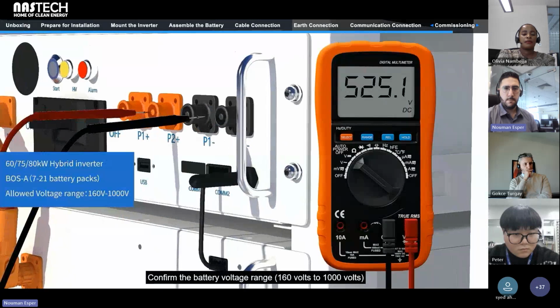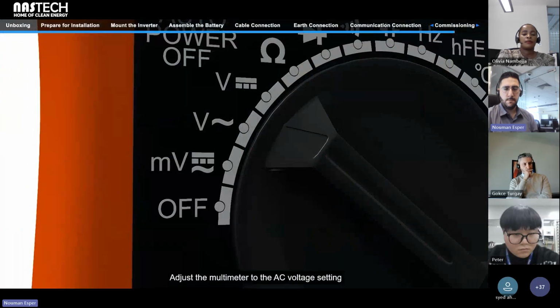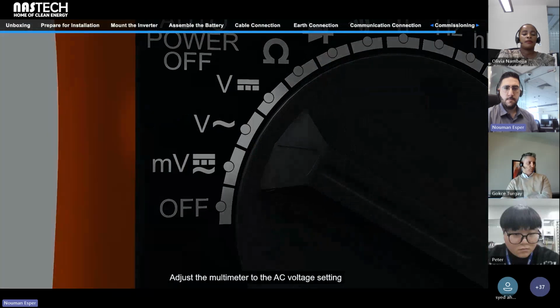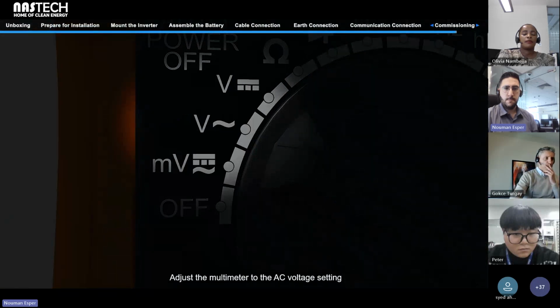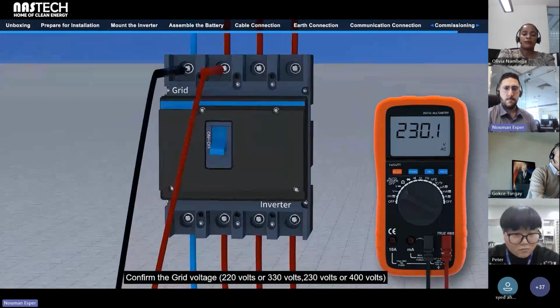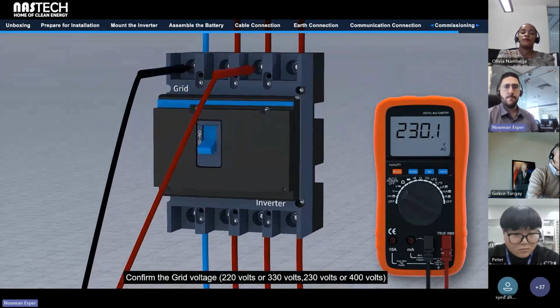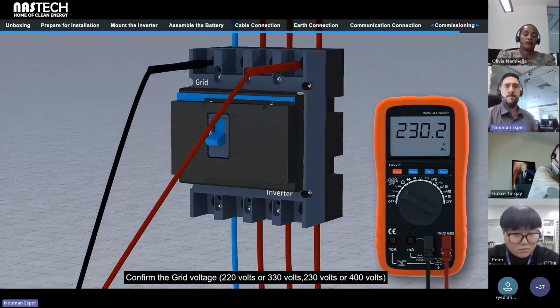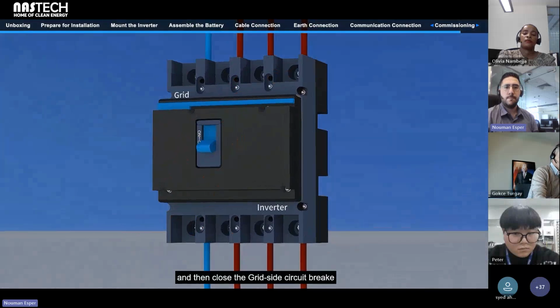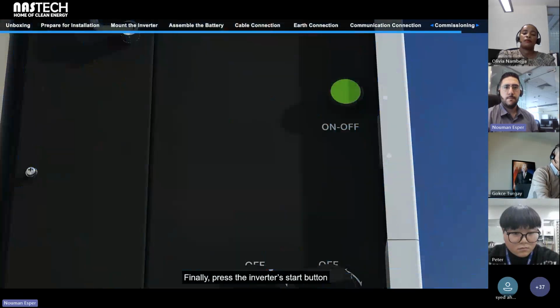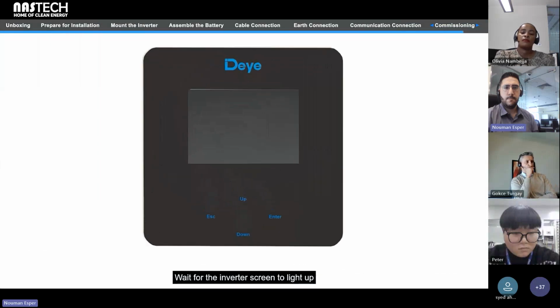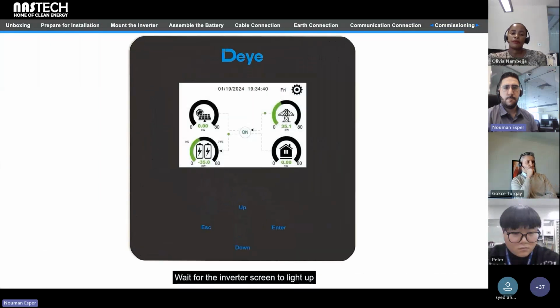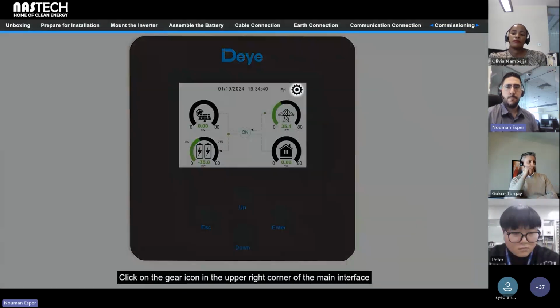Confirm the battery voltage range, 160 volts to 1000 volts. Adjust the multimeter to the AC voltage setting. Confirm the grid voltage, 220 volts or 330 volts, 230 volts or 400 volts, and then close the grid side circuit breaker. Finally, press the inverter's start button. Wait for the inverter screen to light up.